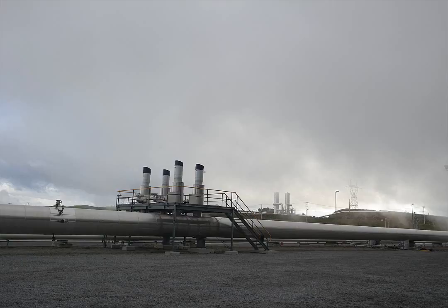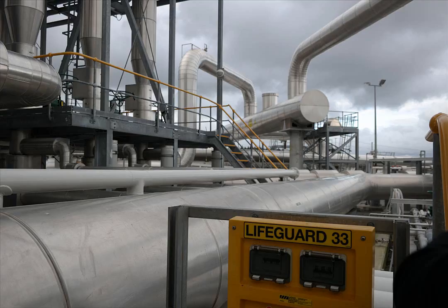Now, these generators, as previously stated, can have between 2 and 4 poles. These here at Te Mihi have 2. Again, they run at 50 hertz. The volts for each one is 11,800. Amperes for the current, 5,319. And an interesting thing about them is the insulation class. The insulation class for these generators, class F, is the most common for international and 50 hertz equipment. Its maximum operation temperature allowed is 155 degrees Celsius, which is 311 degrees Fahrenheit.